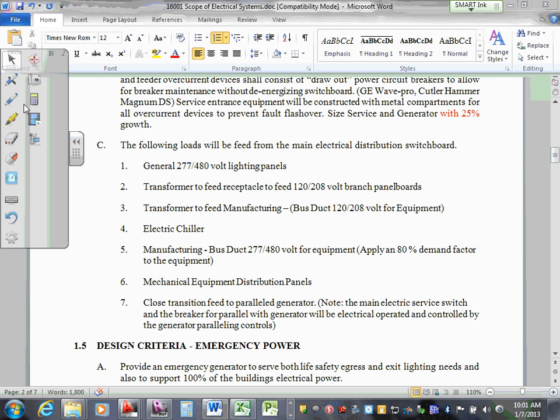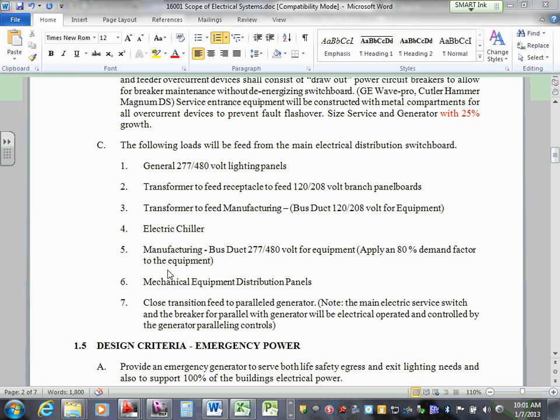Electric chiller is a large block of load that'll come out of that main service switchboard. In the manufacturing, we also have some 480 volt equipment, so we're looking at some additional bus duct at 480 to feed the larger equipment within that manufacturing space. You'll need to come up with a solution for a smaller collection of mechanical equipment. You may feed a distribution panel out of the main switchboard that'll feed a collection of mechanical loads.